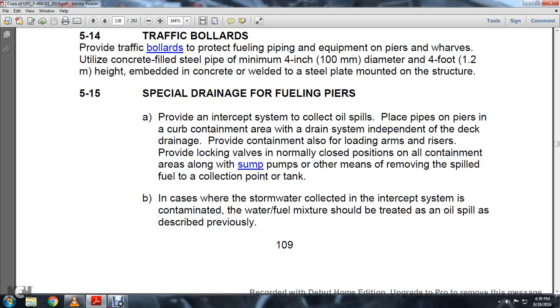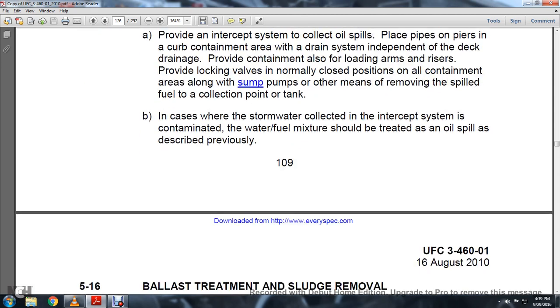Section 5.15 Special Drainage: For fueling piers, provide an interception system to collect oil spills placed in the pipe at the piers, with a curb containment area with a drain system independent of the general drainage. Provide contaminant collection at loading arm risers. Provide locking valves normally in the closed position on oil containment lines. Use sump pumps or other means to remove spilled fuel at the collection point. Where stormwater collected by the intercepted system is contaminated, the water-fuel mixture should be treated as an oil spill as directed previously.